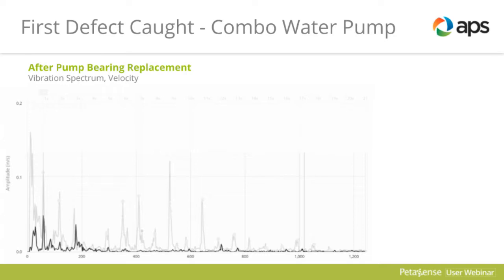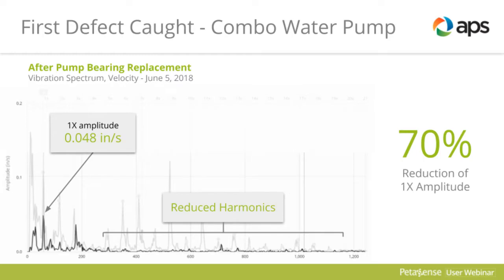And then the plant replaced the pump, and this was the reading that we took after the pump was repaired. As you can see, the one-time amplitude dropped significantly, and the harmonics dropped significantly also. You can see the high-frequency noise floor all went down also.